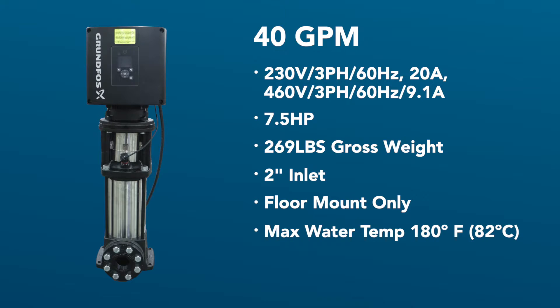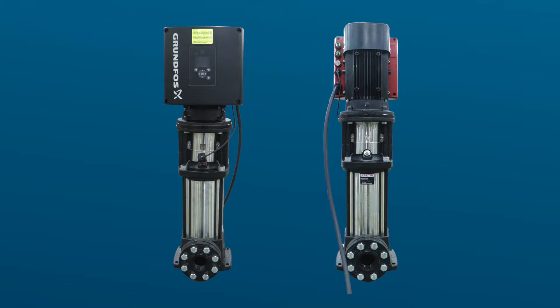The Grundfos pumps have been designed to accept up to 180-degree inlet water. It is important to note that this pump will auto-correct rotation and does not need to be checked or changed. Now I'll take you through the locations of the main components of the 40 GPM Grundfos pump.